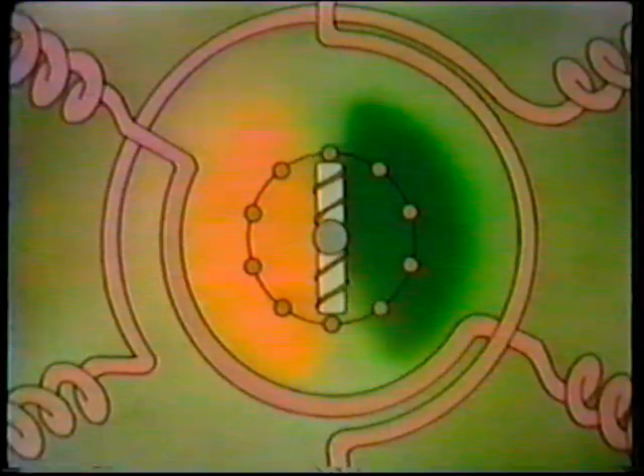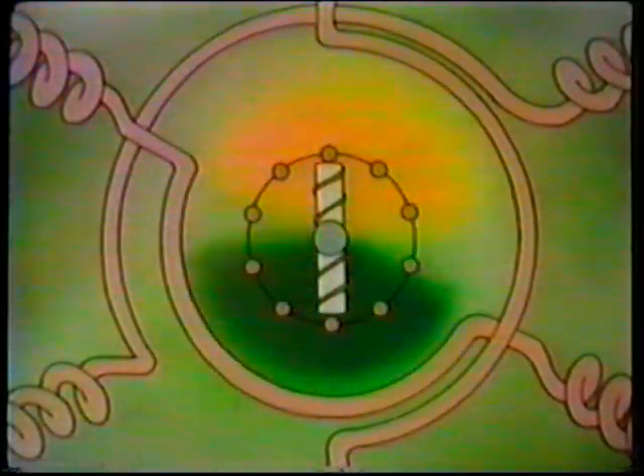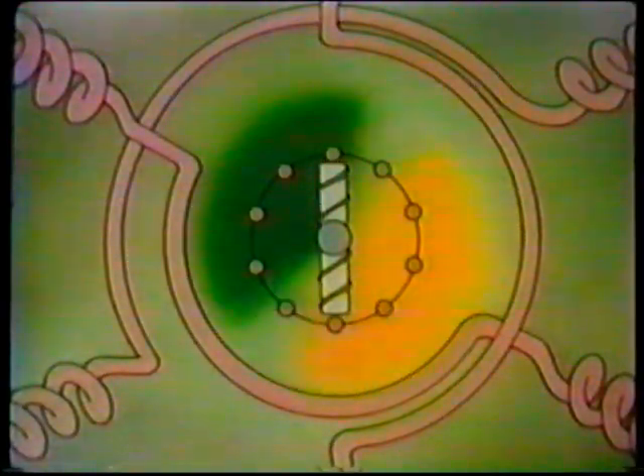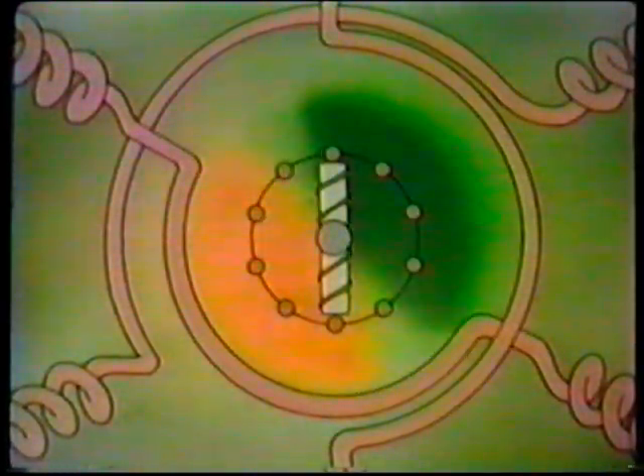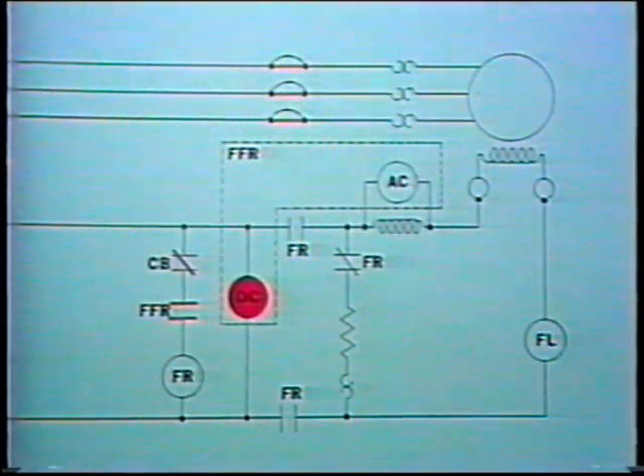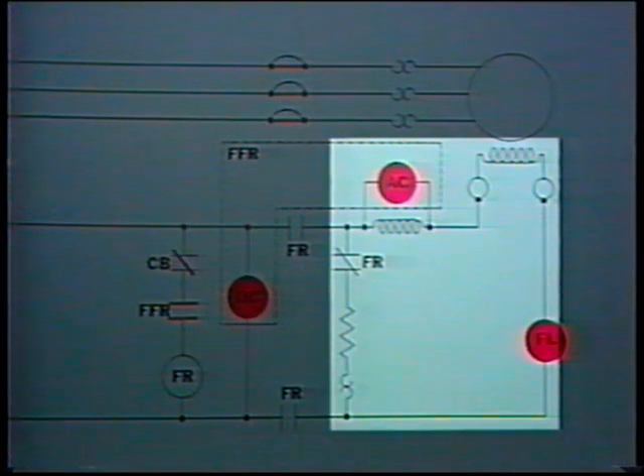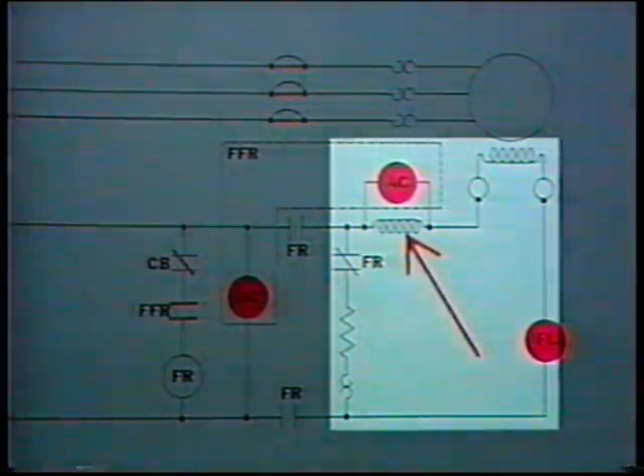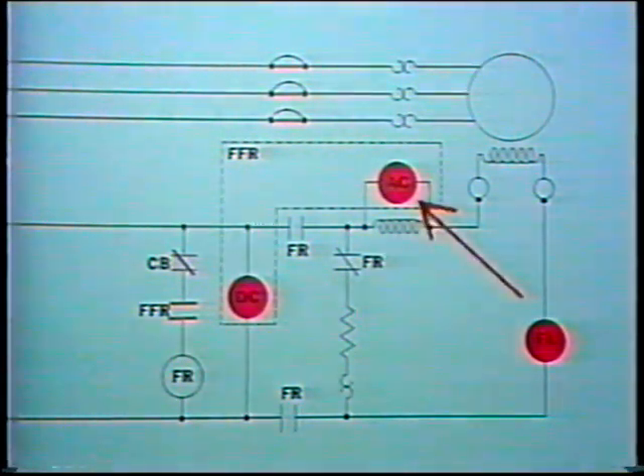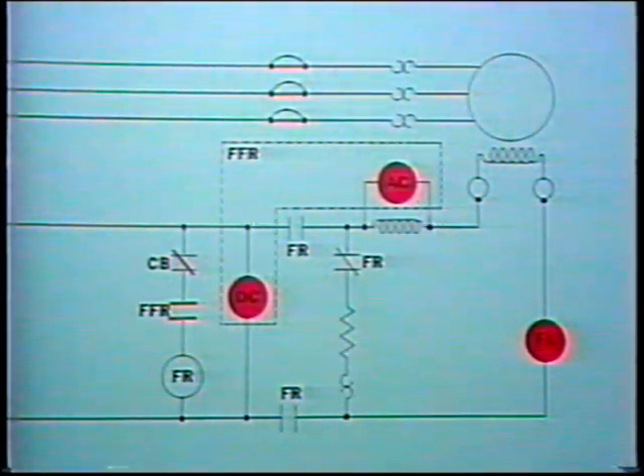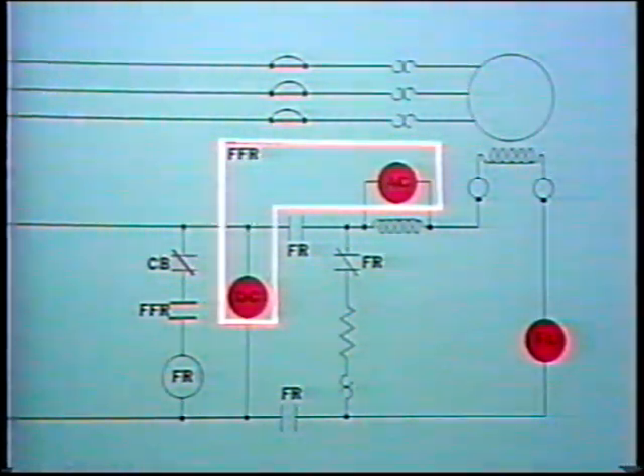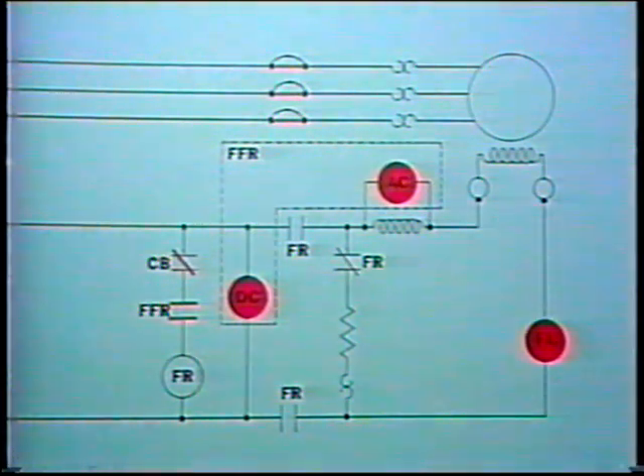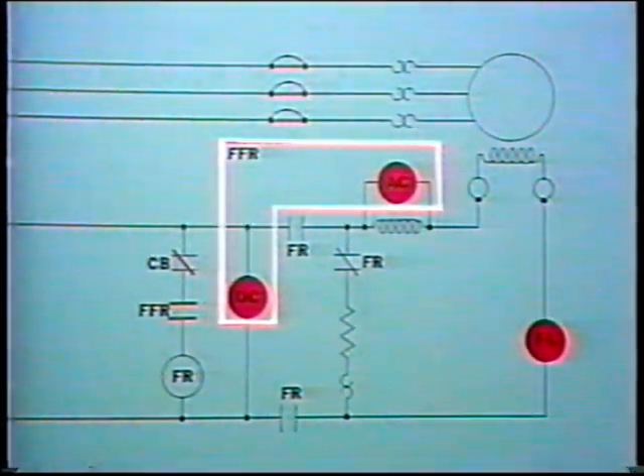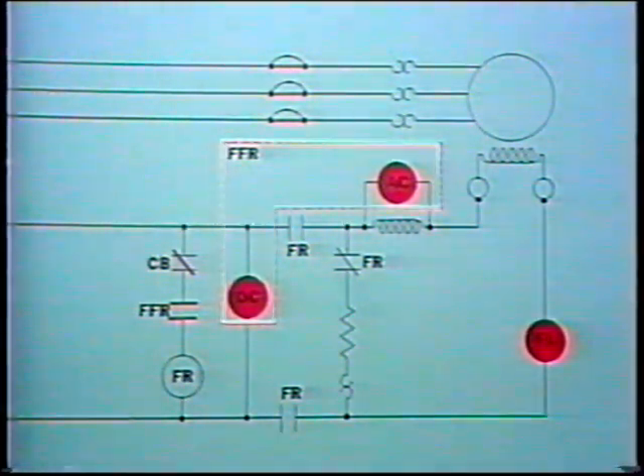As the stator field rotates, its magnetic poles sweep across the rotor, inducing an alternating current in the amortisseur bars of the rotor and the rotor windings. The induced alternating current flows through this part of the circuit. An inductor is part of this circuit. The inductor is connected in parallel with an AC coil. The AC coil is part of a component called a field frequency relay. The relay also has a DC coil in it. The main function of a field frequency relay is to control when the rotor windings should be energized.